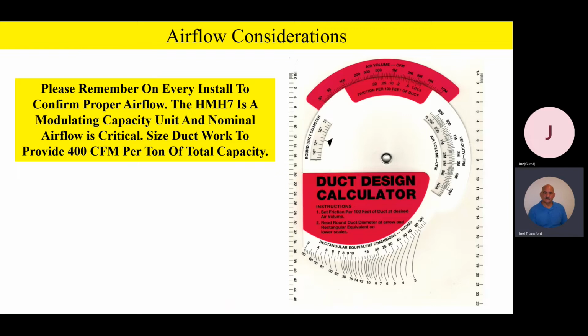So airflow is really critical on any modulating system. It doesn't matter whose brand it is. If you don't have the proper airflow, the modulating system is not going to be able to sense what capacity it should be at if it has inadequate airflow. So it's important that we stress to our customers to double check that airflow and make sure the ductwork is sized to provide 400 CFM per ton of total capacity.